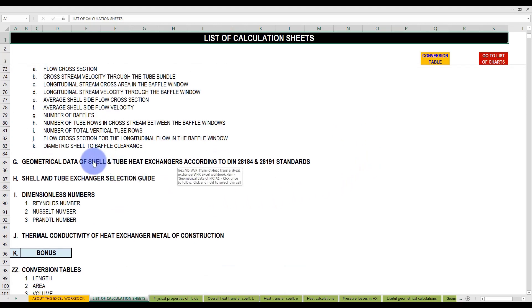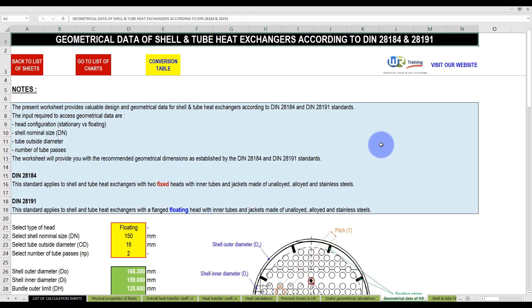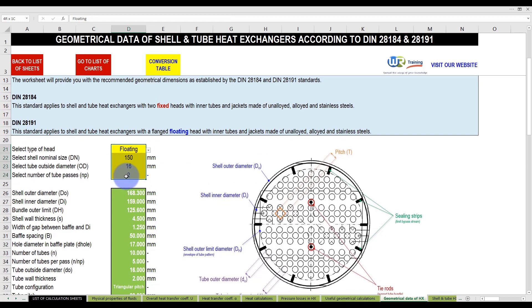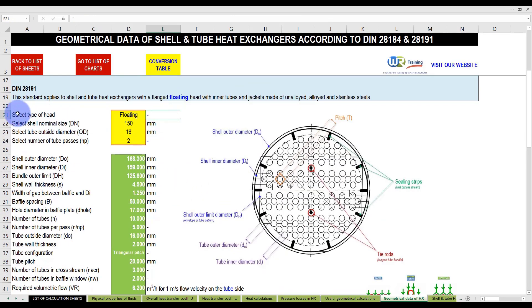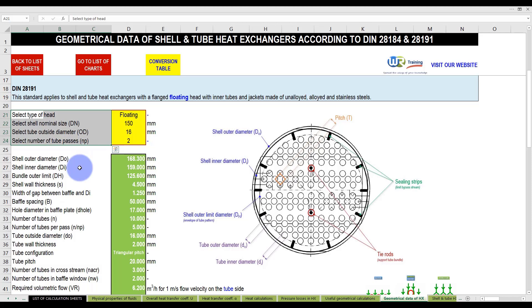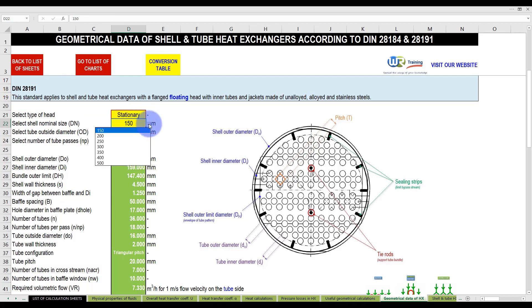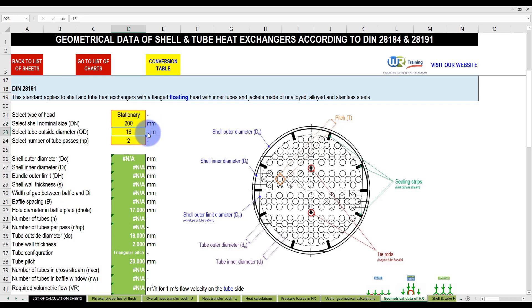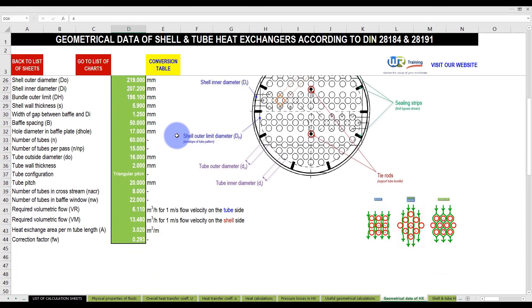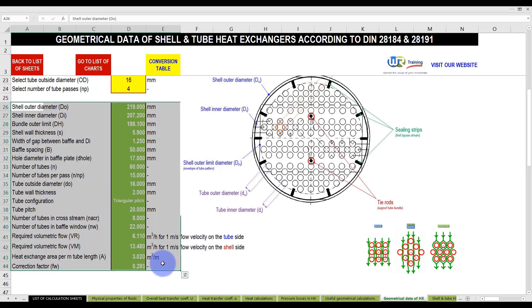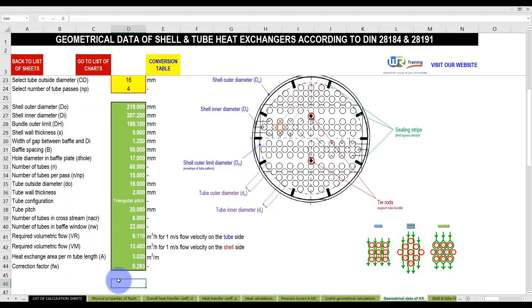To do that, we will scroll down and click on 'Geometrical Data of Shell and Tube Heat Exchangers.' In this example, to access the TEMA recommendations, we need to specify four parameters: the type of exchanger head, the shell nominal size, the tube outside diameter, and the number of tube passes. Let's suppose we have a shell and tube heat exchanger with a stationary head, a shell nominal size of 200 millimeters, a tube outside diameter of 16 millimeters, and four tube passes. If you scroll down, you will see all the recommended design and dimensions according to the latest TEMA standards. For example, TEMA recommends a triangular pitch for the tube layout.